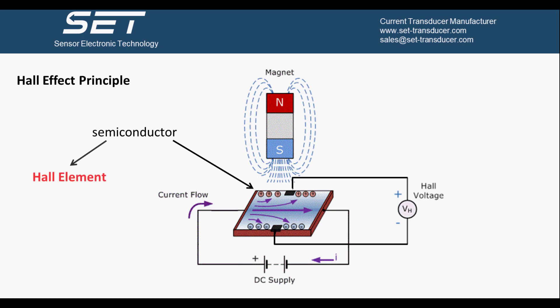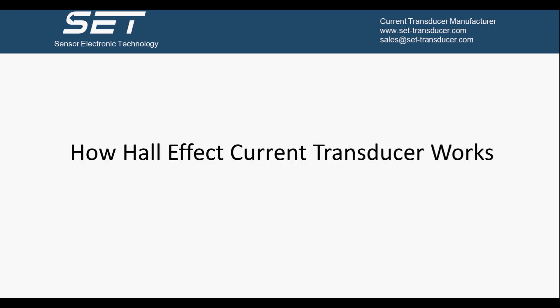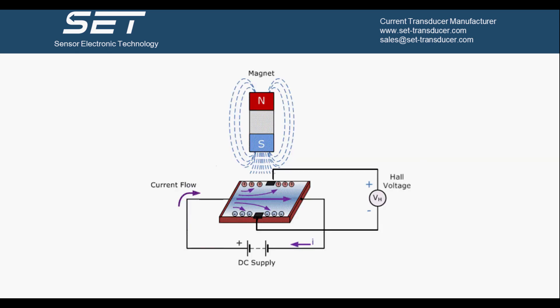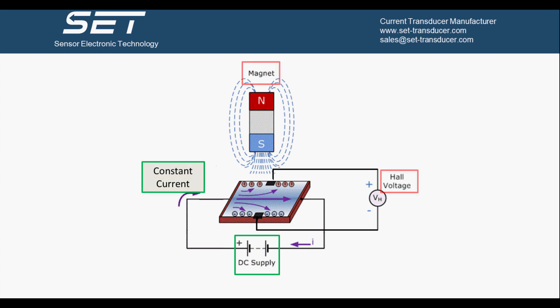The piece of semiconductor is also called a Hall Effect Element. Now let's see how Hall Effect Current Transducer works. According to the proportional relationship between the Hall Voltage, the magnetic field strength, and control current, we can design a device which provides a constant control current, so the Hall Voltage is only affected by the magnetic field strength.